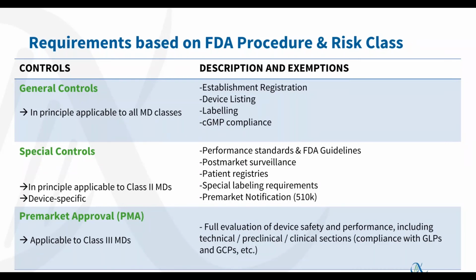The device itself needs to be registered. This is known as device listing. And then there are some general labeling requirements, so that the labeling and the instructions for use need to comply with general FDA controls and guidances. And then devices in the United States should be manufactured in accordance with the so-called current good manufacturing practices, or these quality system regulations that we mentioned before. This is the ISO 13485. It's not directly accepted by FDA, but there's a project ongoing whereby FDA will include ISO 13485 as a CGMP compliance standard, so that in the near future it will be sufficient that devices are manufactured under ISO 13485 also in the United States.